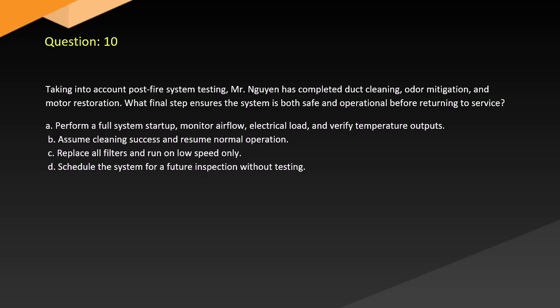Question 10. Taking into account post-fire system testing, Mr. Nguyen has completed duct cleaning, odor mitigation, and motor restoration. What final step ensures the system is both safe and operational before returning to service? A. Perform a full system startup, monitor airflow, electrical load, and verify temperature outputs. B. Assume cleaning success and resume normal operation. C. Replace all filters and run on low speed only. D. Schedule the system for a future inspection without testing.